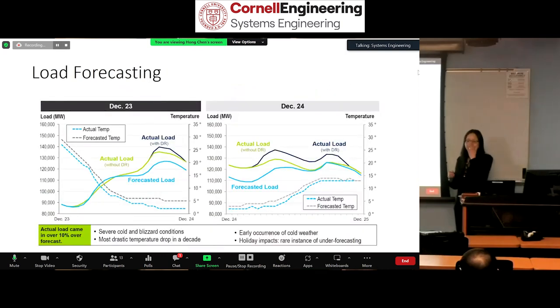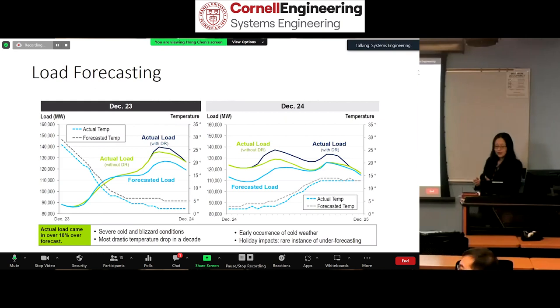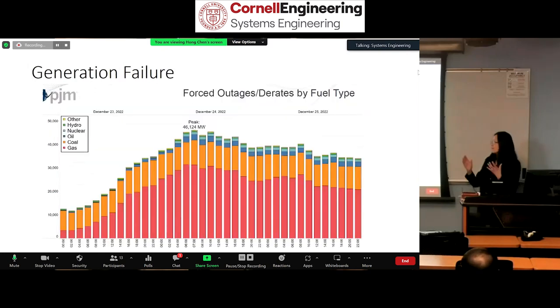So the whole story from this winter storm Elliott I wanted to mention here: load-wise it's definitely an outlier because the temperature dropped 29 degrees on the same day. We never had this before, we don't have historic data for that. So you can see the forecast load is significantly lower than actual load. We were not prepared because the load forecast was not that high, and we did not know the generation tripping could be so high.